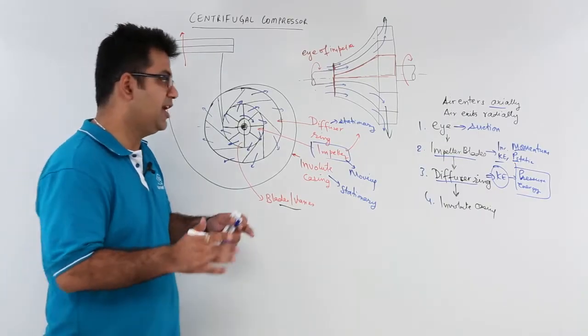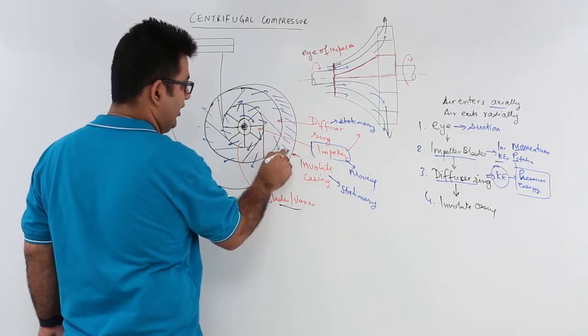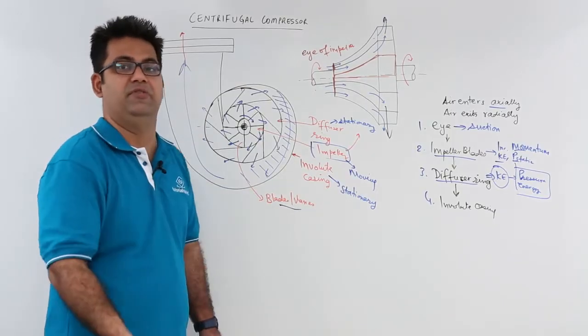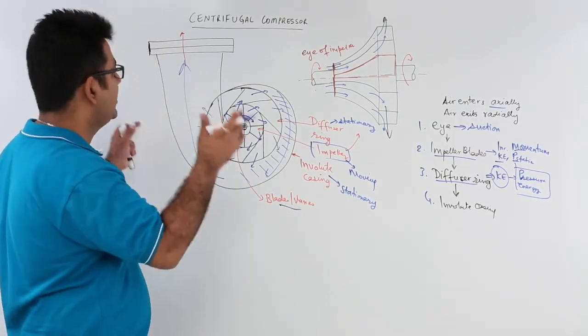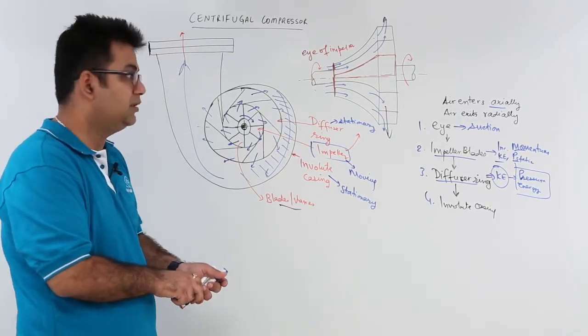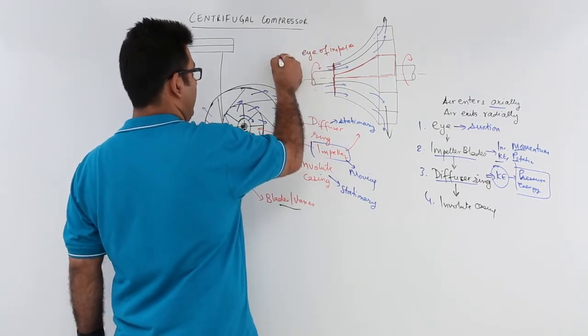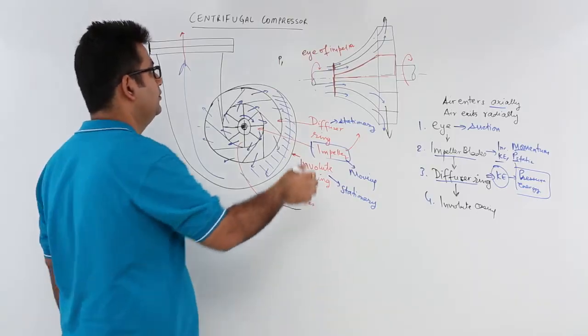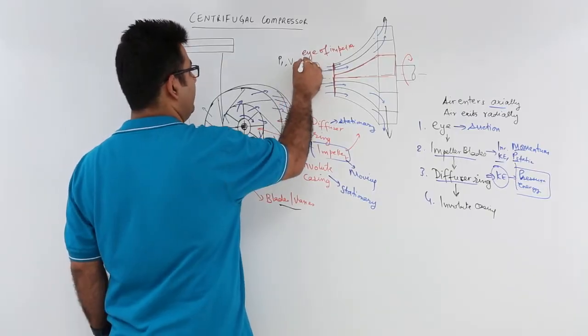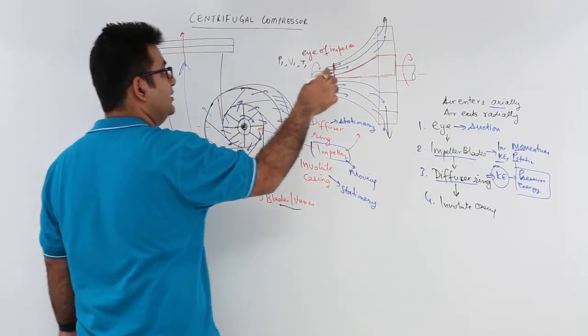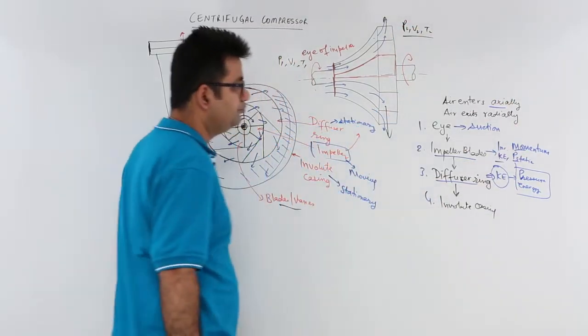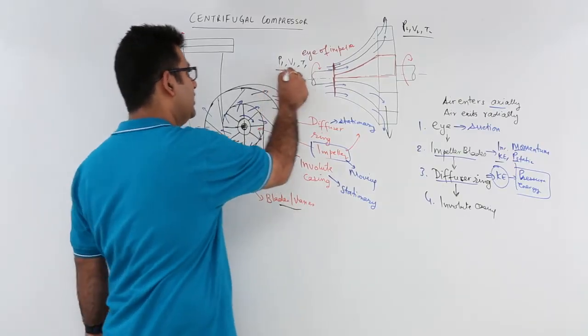Now this high pressure energy air is now taken into this involute casing. It gets collected over here, and it is pushed out of this involute casing into the receiver. So this is how a centrifugal compressor works. Let us say, at the inlet part, at the eye, you have pressure P1, which is almost equal to the atmospheric pressure. The velocity with which it comes in, it is V1, and the temperature is T1. At exit, let us say it is P2, V2, and T2. So this is the inlet condition, and this is the outlet condition.